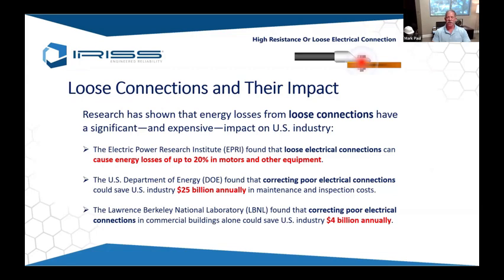So what's a thermochromic clip or indicator really going to capture? The reality is, anywhere there's an electrical connection where two pieces are connected together, or a part of an electrical component that gets a lot of flexing, movement, or vibration, over time these connections can loosen or break completely. When you get a loose connection, there's higher resistance, and that generates heat.